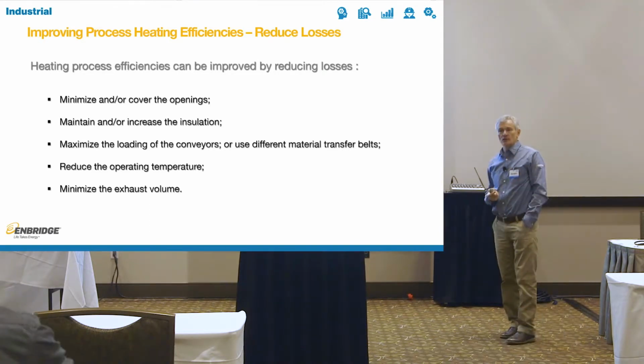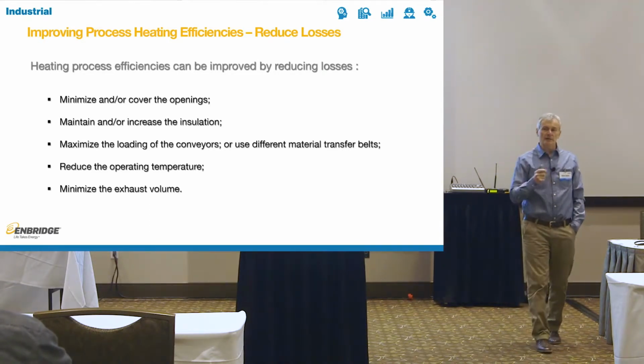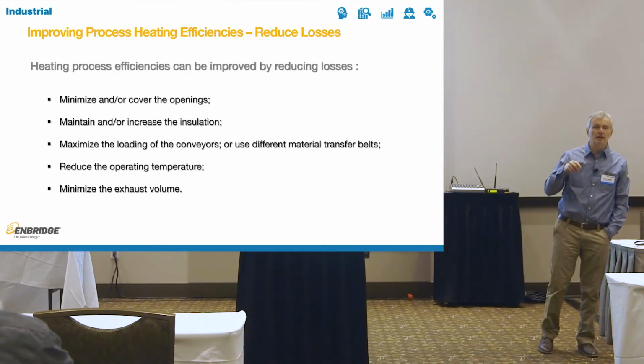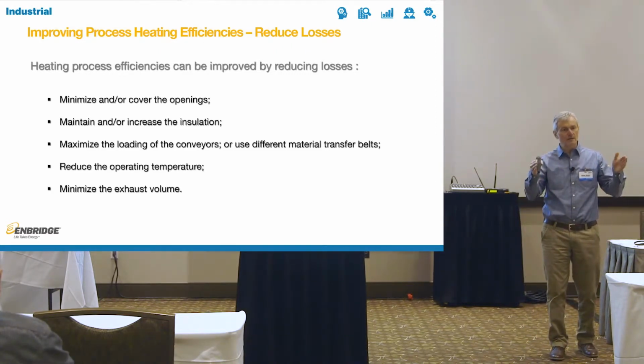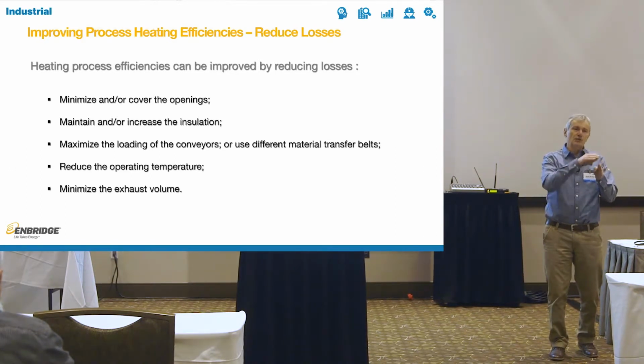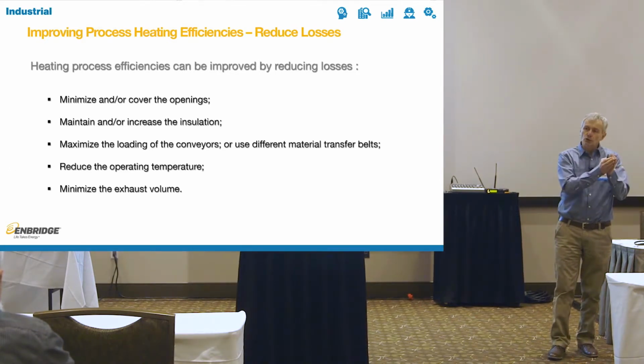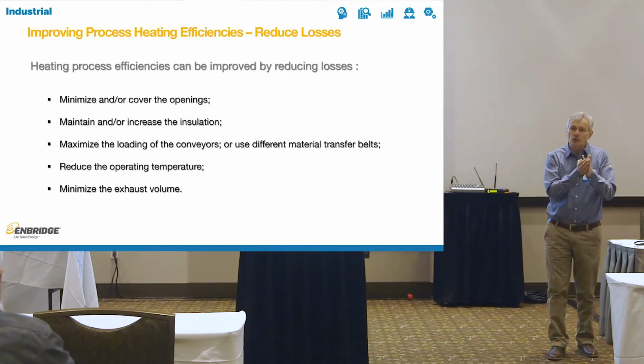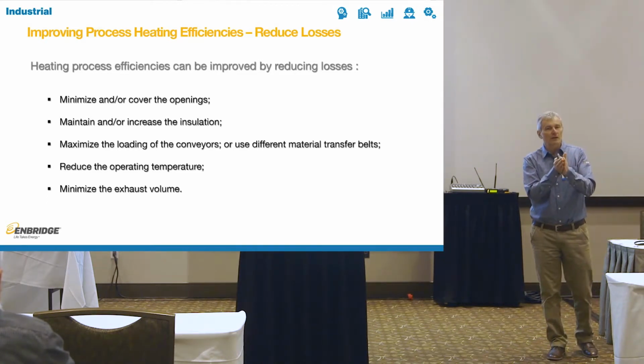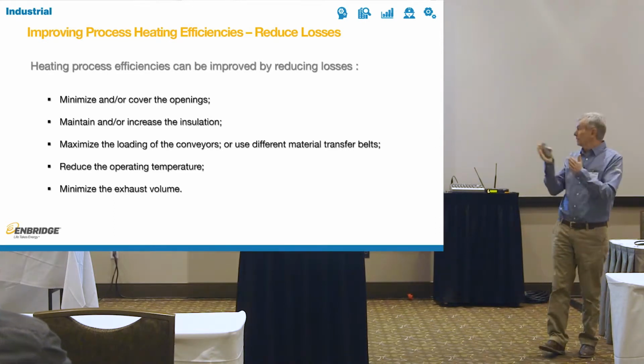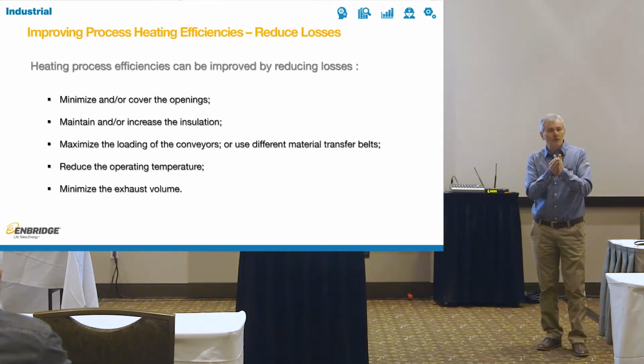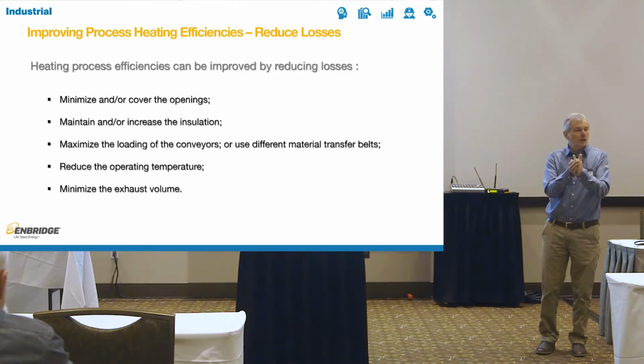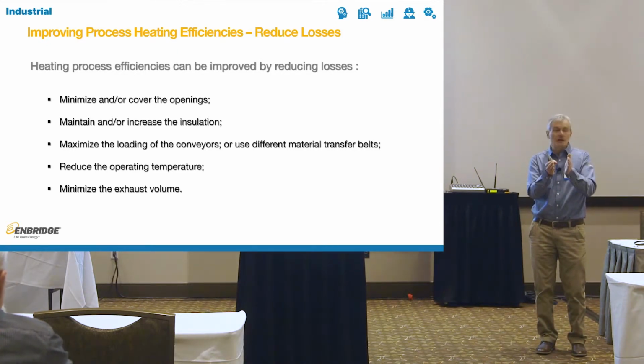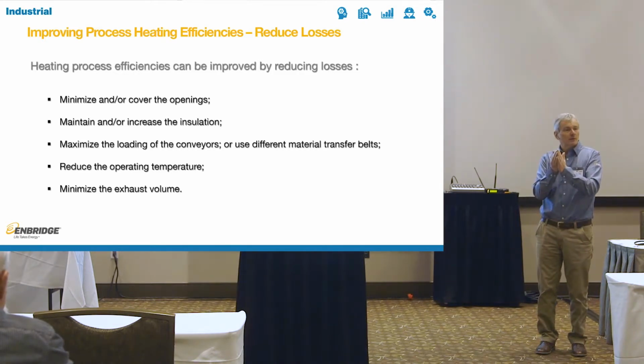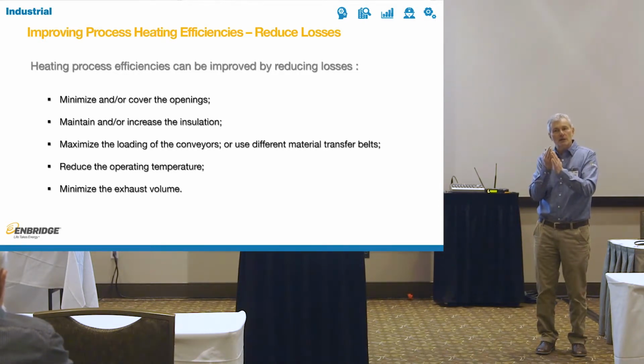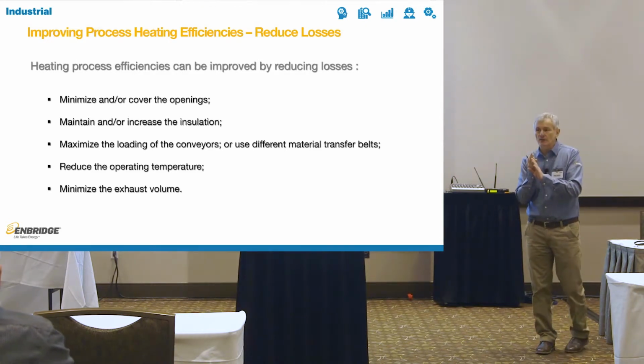Maintain or increase the insulation, another part. People usually take that to mean add insulation. I would not advise that blindly, because insulation is designed to be a certain size, and if you just put additional insulation on the insulation you have, you could create potential for condensation. You could actually degrade your equipment much faster than otherwise. So what I mean by maintain or increase the insulation is, if you have, say, 4 or 6-inch panels, can you afford to put in 8-inch panels? Does that make sense? But more importantly, do you have any gaps? Did the insulation get squished around the metal structure? That's where you're going to get a lot of heat losses.